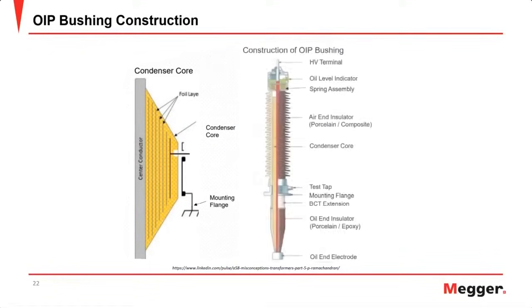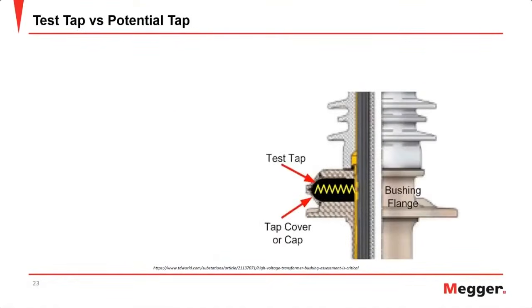And then here is a little bit more detail on how these bushings are constructed. I won't cover every different part of the bushing here today. The part that I really want to focus on is that tap that I talked a little bit about earlier. This tap can come in two different flavors, and for low voltage bushings, so these are bushings that are less than 69 kV, this is referred to as a test tap.